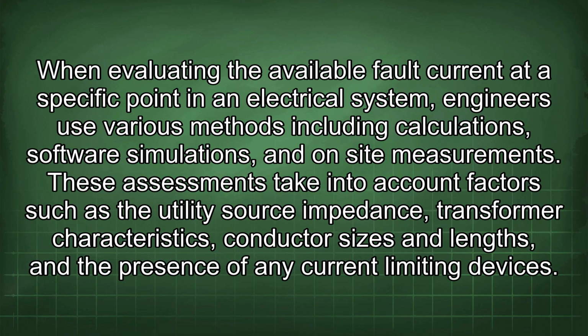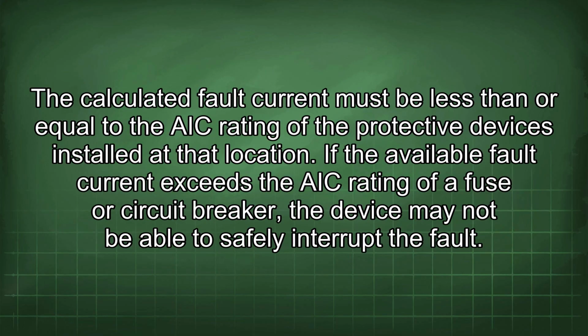When evaluating the available fault current at a specific point in an electrical system, engineers use various methods including calculations, software simulations, and on-site measurements. These assessments take into account factors such as the utility source impedance, transformer characteristics, conductor sizes and lengths, and the presence of any current limiting devices. The calculated fault current must be less than or equal to the AIC rating of the protective devices installed at that location.